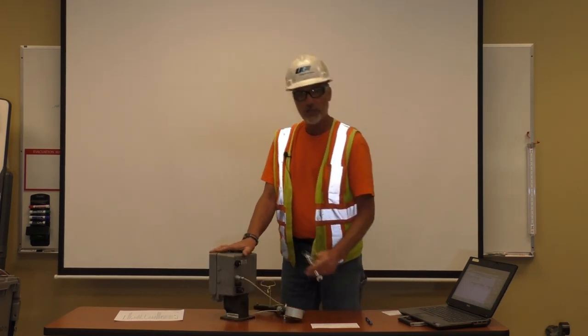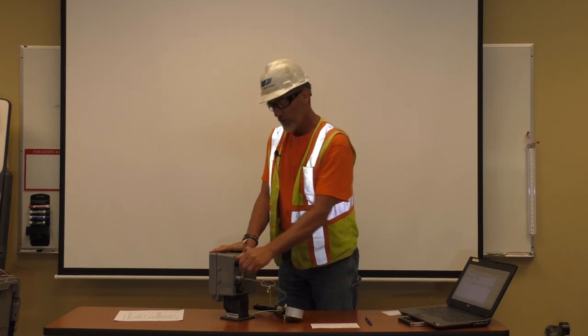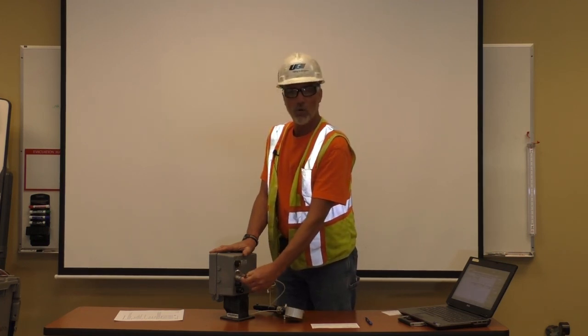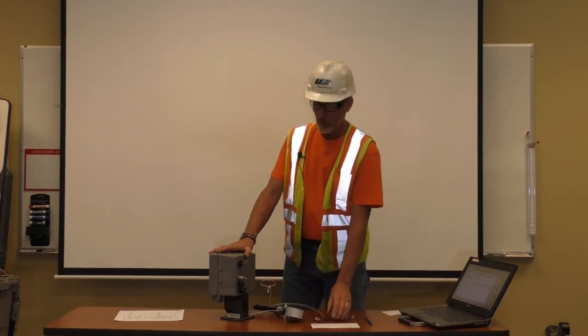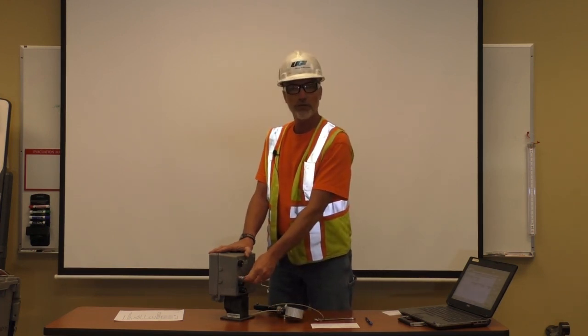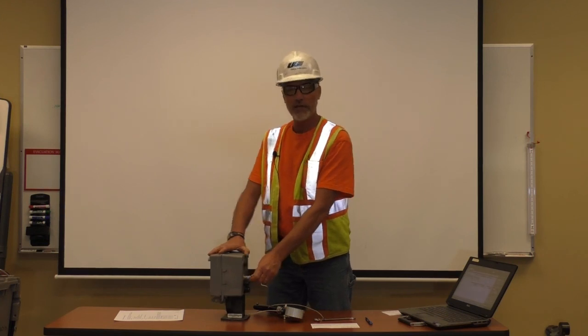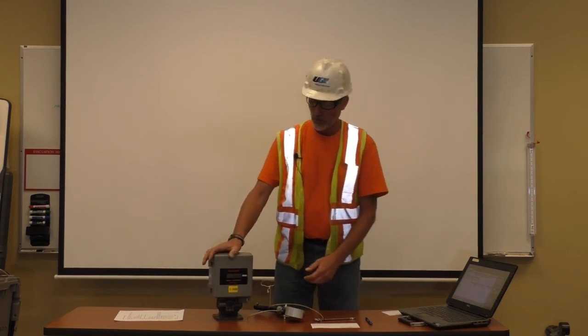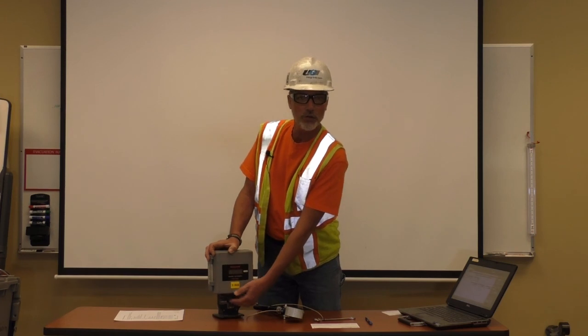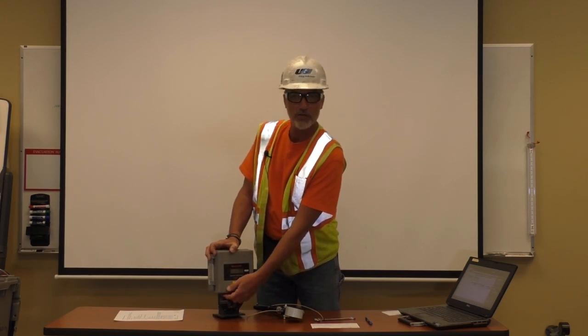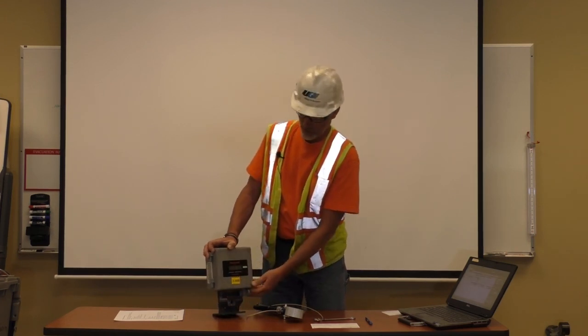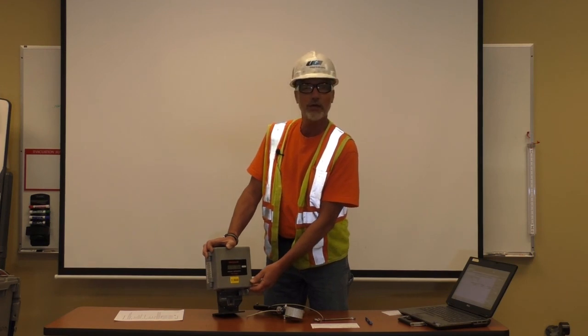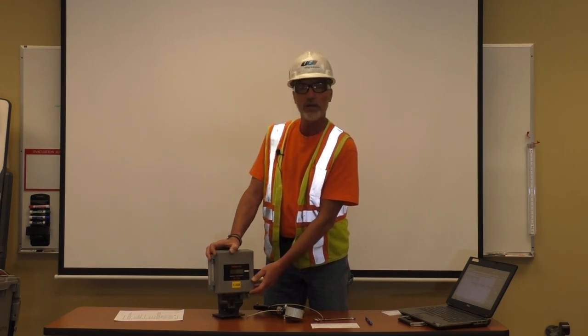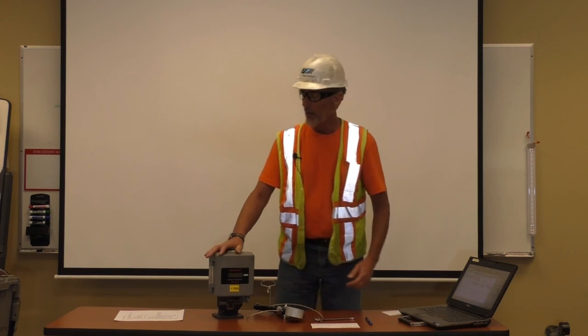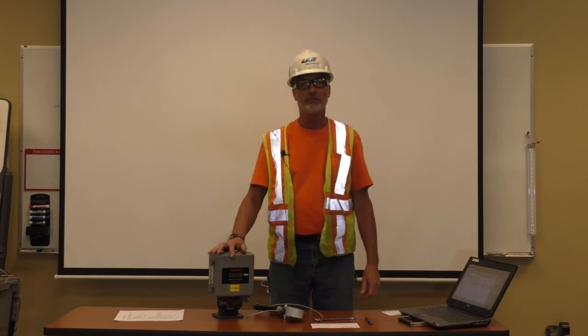To finish, you want to disconnect your gauge from your device or from your isolation manifold. Reinstall your pressure tubing to the back of the device. Check for leaks. Scroll through your device to the pressure to make sure that you have the pressure back into your device. And also check your battery voltage, and if need be, change the batteries. And this test is complete.